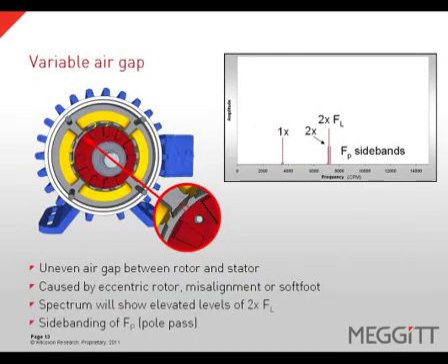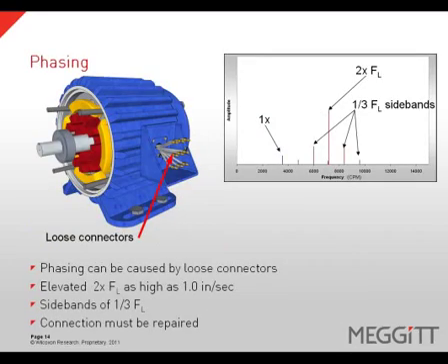Variable air gap is an uneven air gap between the rotor and the stator, typically caused by an eccentric rotor, misalignment, or soft foot. The spectrum will show elevated levels of two-times line frequency, with sidebanding around two-times line frequency spaced at pole pass frequency. Phasing can be caused by loose connectors and can be identified in the vibration spectrum by elevated levels of two-times line frequency with amplitudes as high as one inch per second. It is typical to see sidebands spaced at one-third line frequency, and when this condition exists, the connections must be repaired.